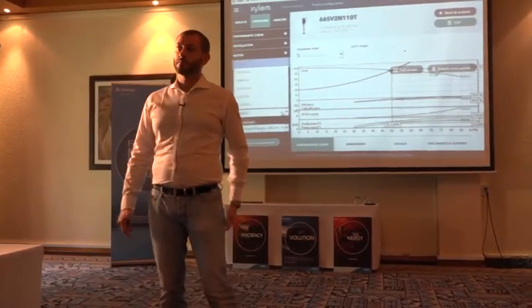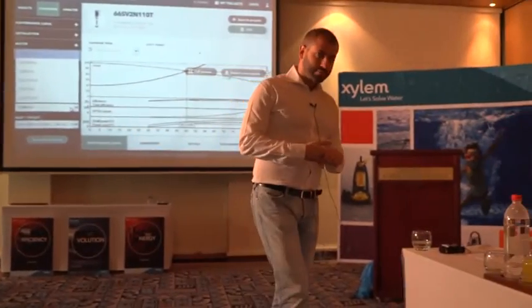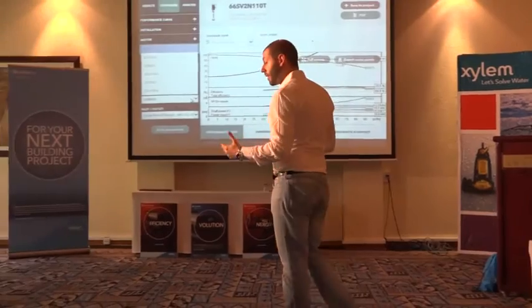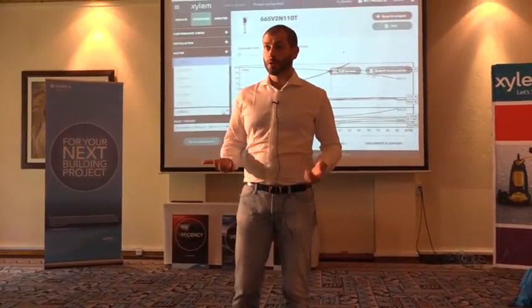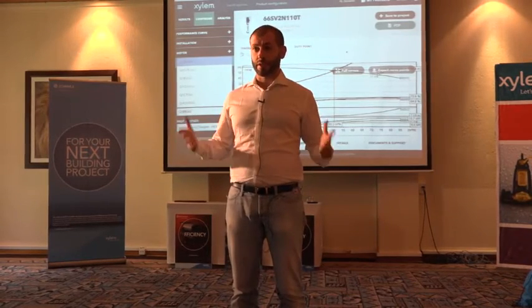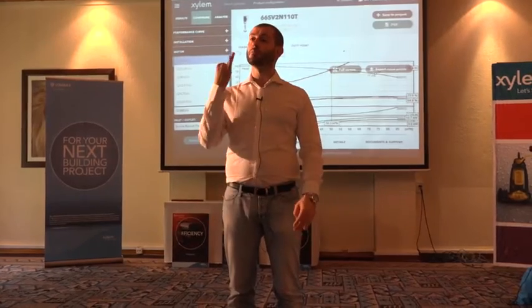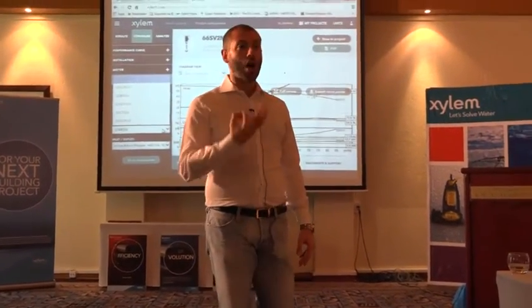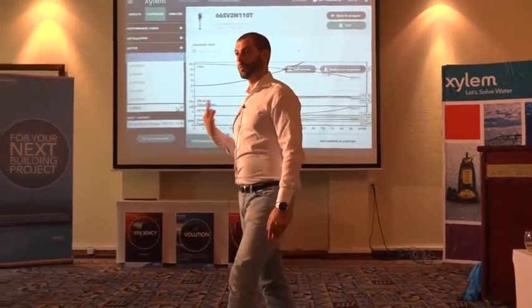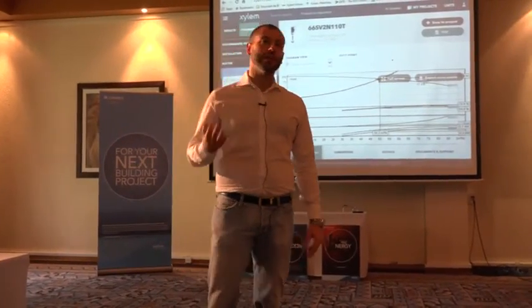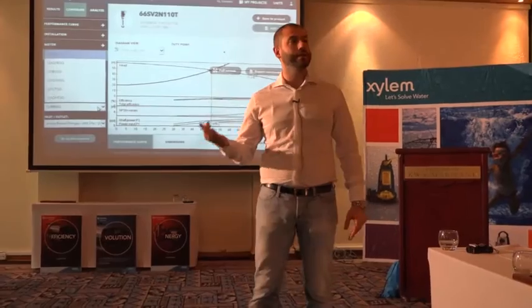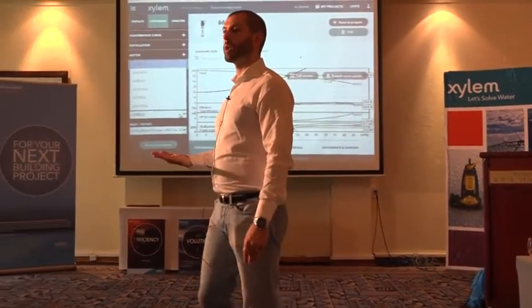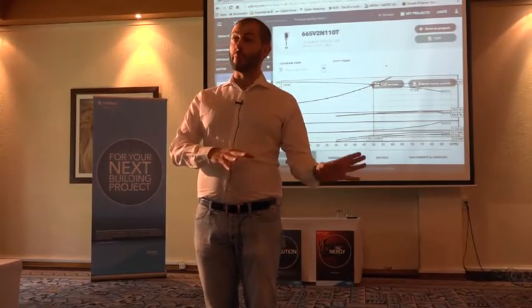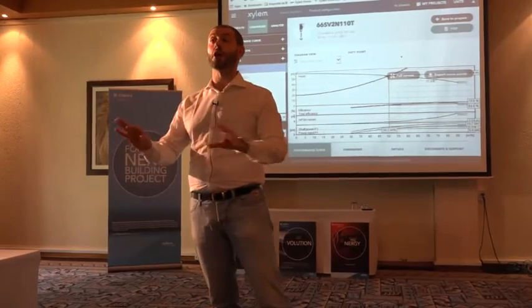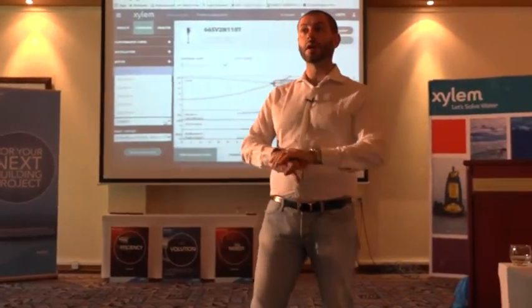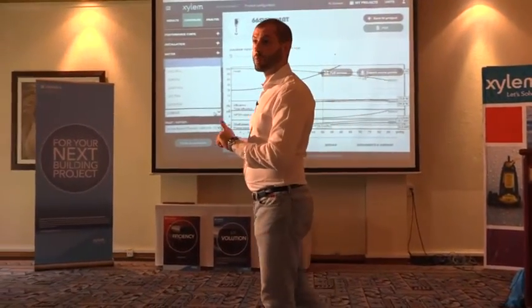The matter is how to select the mechanical seal. So, if I know it, okay, I know that. But what to select and how to select? Here is strictly related to your application. So I would say that in commercial building service, you have 3 options. For you, 2. Why? Because the third is only for boiler application. It means that you need to have water that is between 140 and 180 degrees. Okay? I don't see so many applications in your countries. In commercial building service, because if we look at the industry, yes. If we look at oil and gas, yes. Looking at commercial building service, I don't see an application with boiler that are pumping water at this temperature.